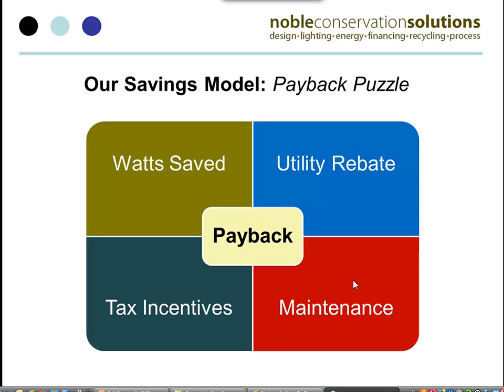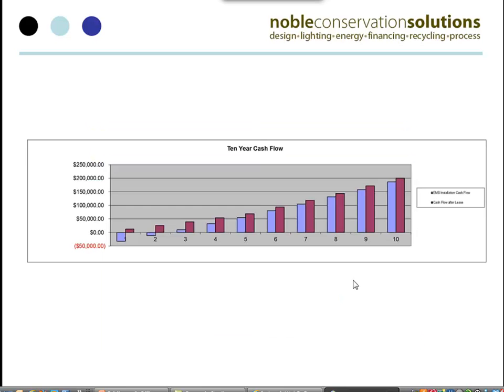We've had situations where people have been up on buildings doing some maintenance on a rooftop heating and cooling unit, and we come to discover that the person did not actually do that maintenance. They smoked a number of cigarettes up on the roof and then came back down, but did not switch out the filters and things like that. Obviously, that's a big waste for that company from an hourly expense standpoint. And just as importantly, swapping out the filters can save about 30% efficiency on it, so it's also a long-term cost savings over time. So again, that red corner, the maintenance, is a key piece of this payback program.